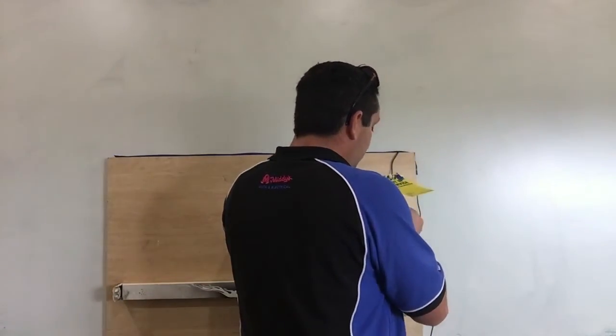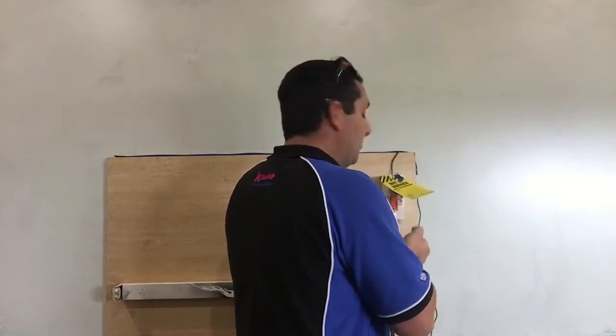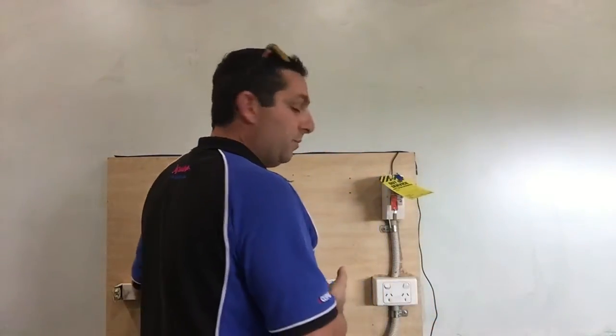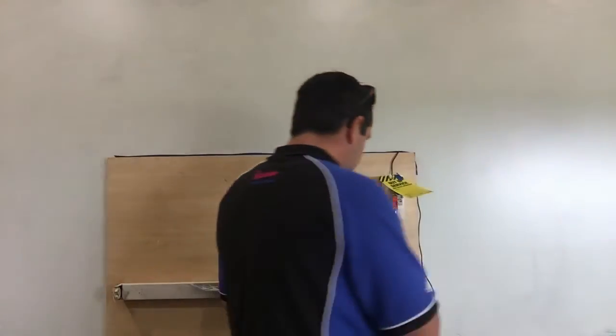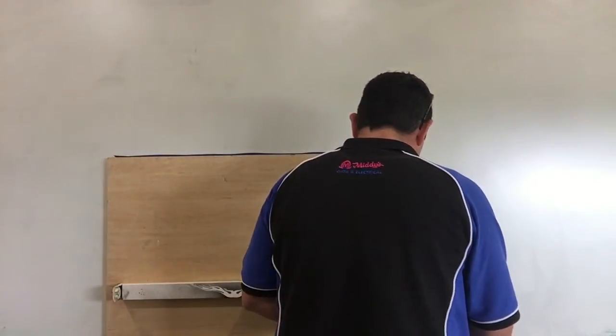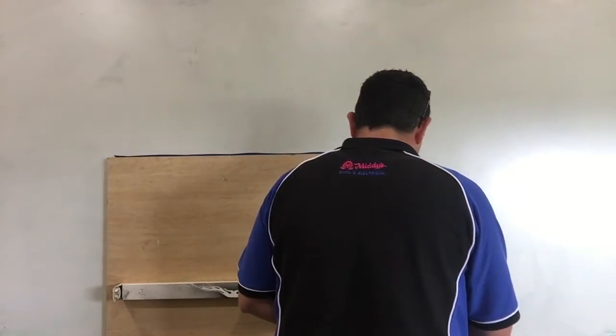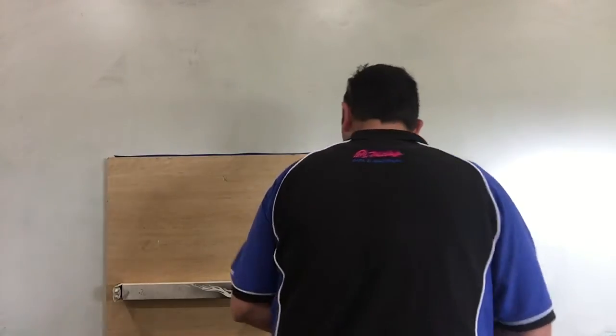Whether we've established yet it's the one that we need or not, we're going to be removing the cover, we're going to be working on an appliance. The last thing we want is for someone to come and turn that circuit on, bringing the key with us. We're going to test our tester: active, neutral, active, earth, neutral, earth.